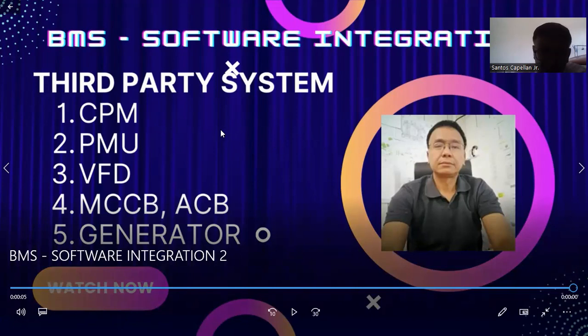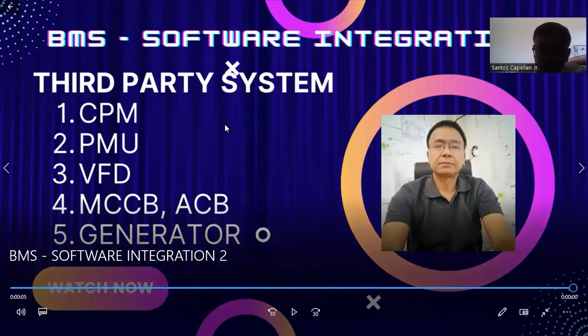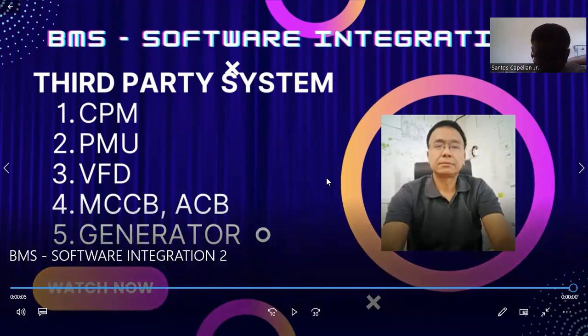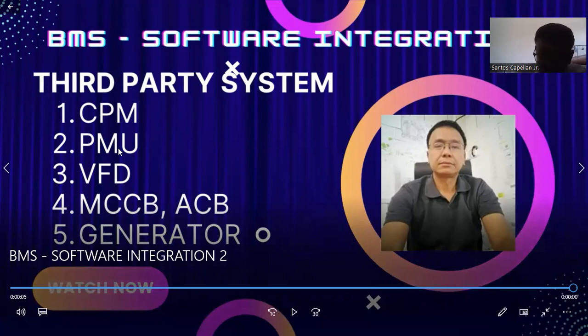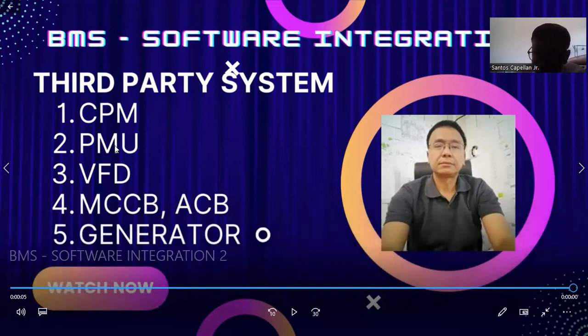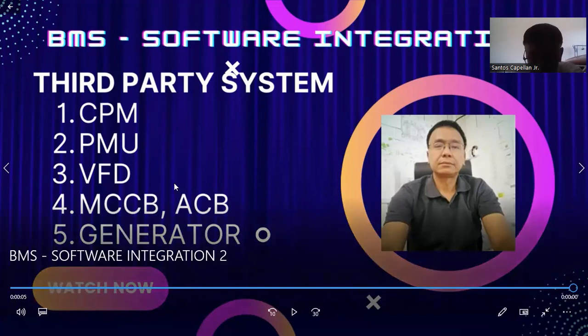My automation server is capable of communicating to different systems because it has two ports, port A and port B. Port A I can dedicate to my BACnet MSTP system. Port B I can dedicate to other third-party systems, like if I have a PMU (Power Monitoring Unit) which communicates through Modbus, or a VFD that also communicates through Modbus.